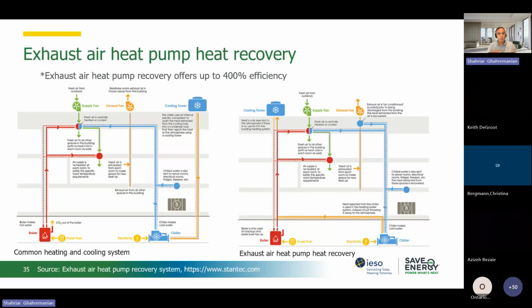In this slide, I show a conventional common heating and cooling system that we have. We have a boiler, and then a chiller connected to a cooling tower, and the exhaust from the washrooms, change rooms, and shower rooms goes directly out. And nobody takes advantage of that. The point is that we cannot bring it back and mix it with the fresh air, or put a wheel on it, because it's dirty air, I would say.